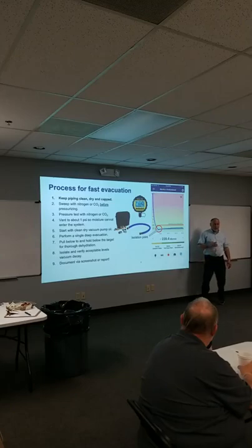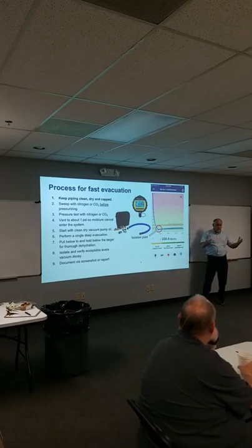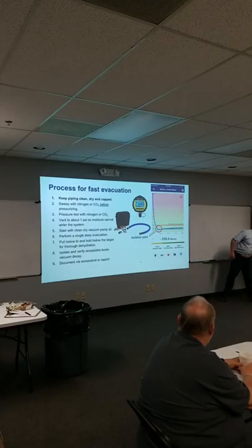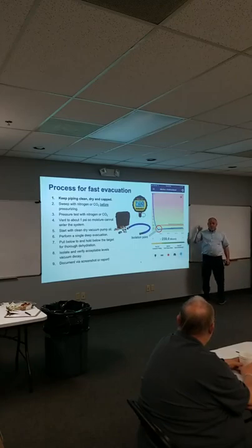It might, a day or two later, but for a full day, if you were to evacuate a tank down today and watch it for a whole weekend, it's going to continually rise all weekend long, because those bonds of moisture are breaking away. As they break away, they create vapor pressure in the tank. And the vapor pressure is continually rising. You're going, whoa, why am I not seeing that in all my other gauges? And it's because they hide it, right? A lot of vacuum gauges go, 500 microns, 250, 100, 50. You don't see all that stuff happen. These have a 1/10 of a micron resolution, so you're gonna see things you'd miss otherwise.